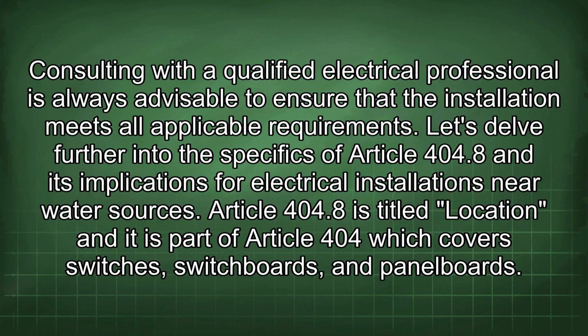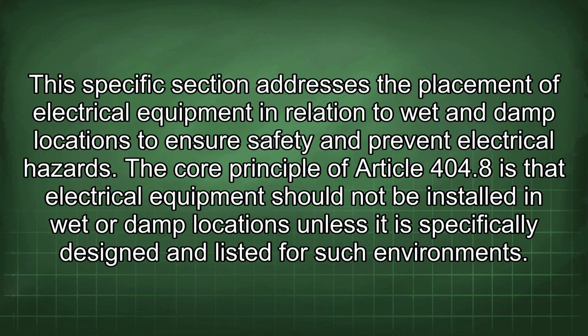Article 404.8 is titled Location, and it is part of Article 404, which covers switches, switchboards, and panel boards. This specific section addresses the placement of electrical equipment in relation to wet and damp locations to ensure safety and prevent electrical hazards. The core principle of Article 404.8 is that electrical equipment should not be installed in wet or damp locations unless it is specifically designed and listed for such environments.